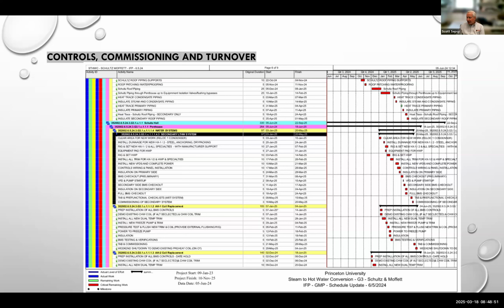You may have to adjust or eliminate setback because with lower delta T's or lower temperatures in the system, spaces may not be able to ramp back up as quickly as possible. So you may have to eliminate or, again, modify the setback schedules to give you more time. Provide adequate training of the new equipment, read-throughs of O&Ms before their training comes. Schedule and videotape the training.